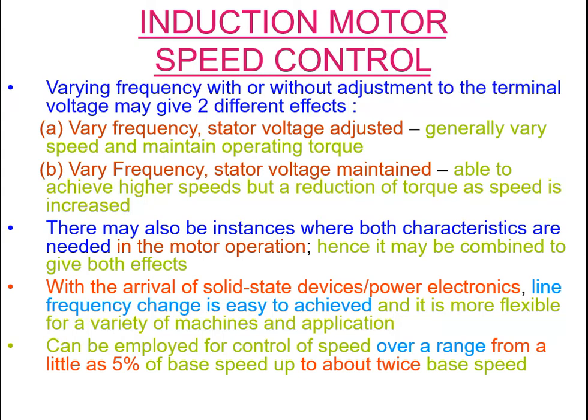Suppose I vary the frequency and maintain the stator voltage at a particular value. In this case, I am able to achieve higher speeds, but the only thing is there is a reduction of torque as speed is increased. So there may be instances where both characteristics are needed in the motor operation. Hence, these effects have to be combined.